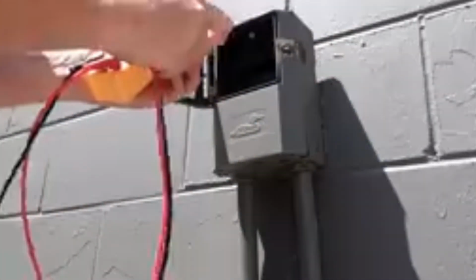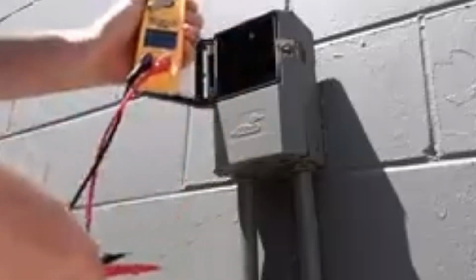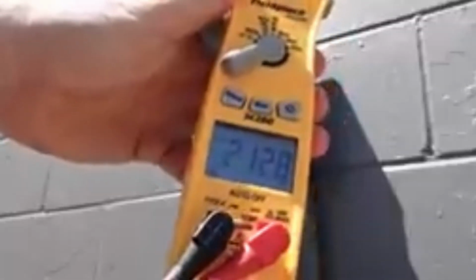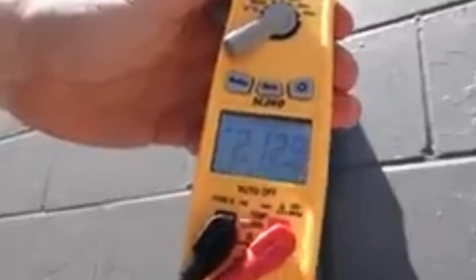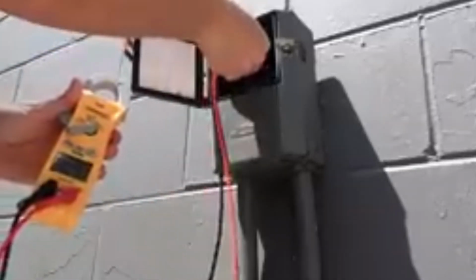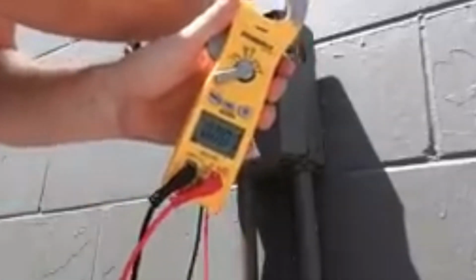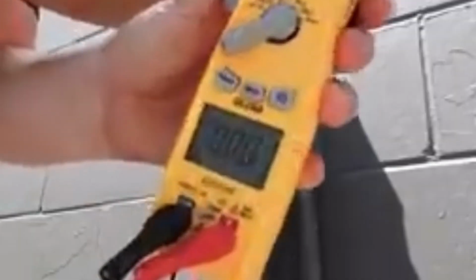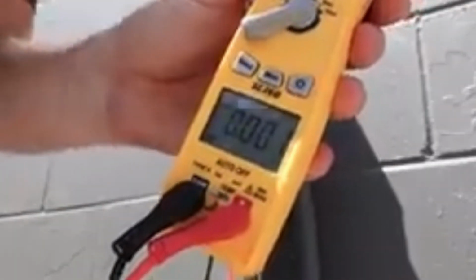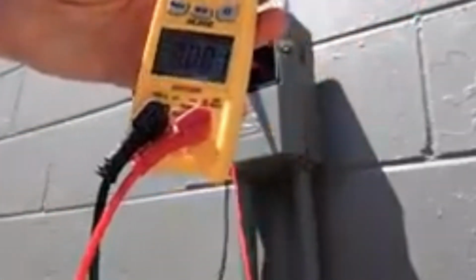Because the disconnect is pulled, I'm going to first measure to a known voltage source just to make sure my meter's working, going from outside to outside, and as you can see, it's measuring 212 volts. Now I'm going to measure going to the unit, and as you can see, I have 0, but I still want to confirm that I have 0 to ground when I get inside the appliance, just to be safe.